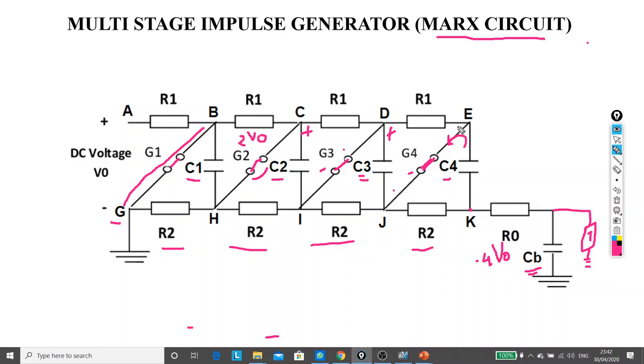In this way, four times the applied voltage is generated as impulse voltage across capacitor Cb. Since Cb is present, the charging time is less and the discharging time is more, so the voltage obtained across Cb has an impulsive nature. This is how we can generate high impulse voltage in the laboratory using a Marx circuit or multi-stage impulse generator, which is useful for testing high voltage insulators in the laboratory.